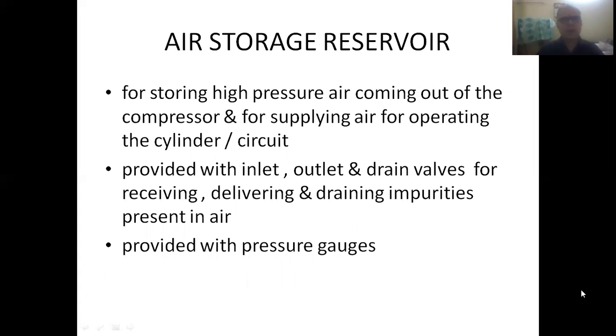So friends, we have talked about storage reservoir. As the name itself implies, it will be receiving high pressure air that is coming out of the compressor. This high pressure air is stored in this reservoir. Ultimately, it is used for operating the piston that is arranged inside the cylinder. So this reservoir is provided with inlet valve, outlet valve, and drain valves also.